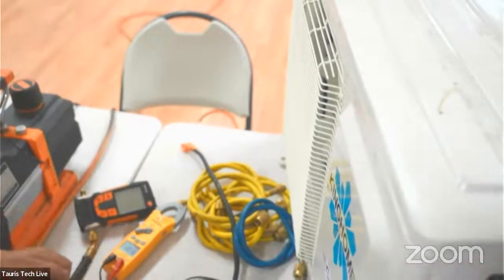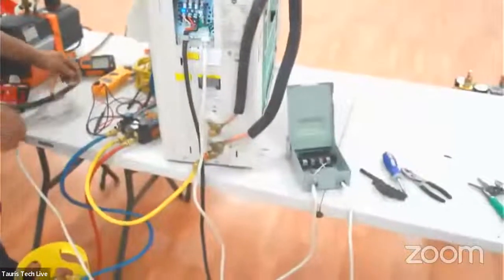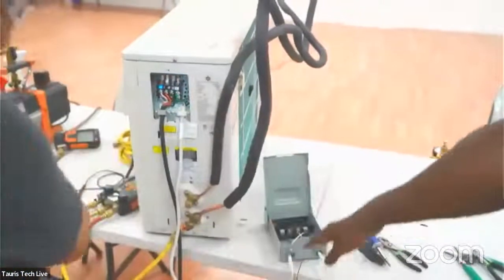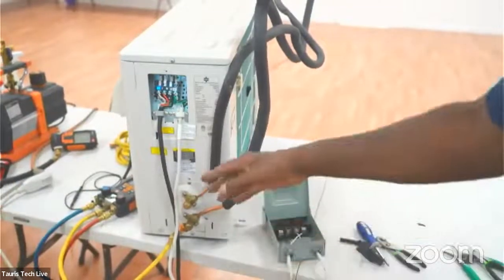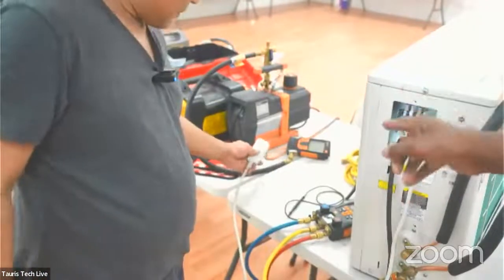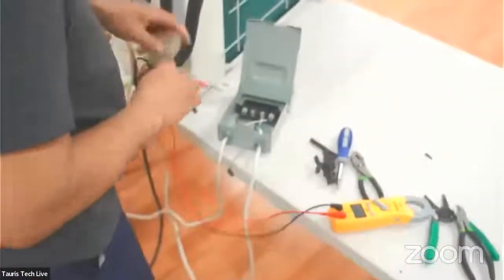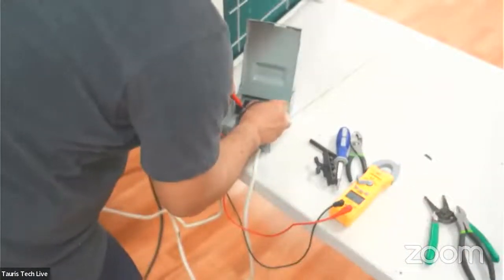Okay. Now plug up your outlet. All right. Now understand something. All this downstream is going to be live. Our circuit breaker or GFCI over there is basically like our circuit breaker. So that's live right there, right? So if you chase your power, you go over here. What we're doing is testing across our hot and our neutral inside of our disconnect switch. This is like our disconnect switch outside the house that we're going to be having for our unit. And it should be basically the same, 123, right?